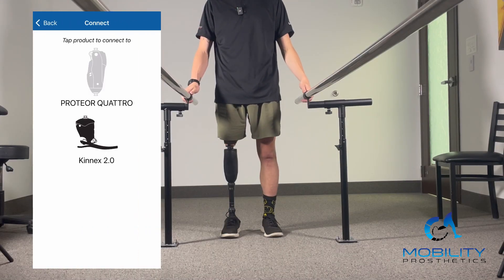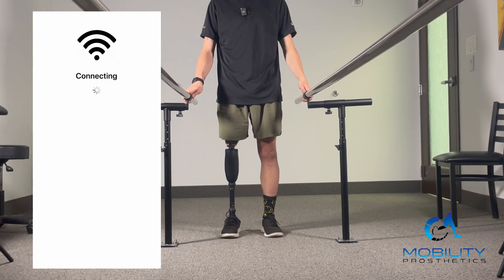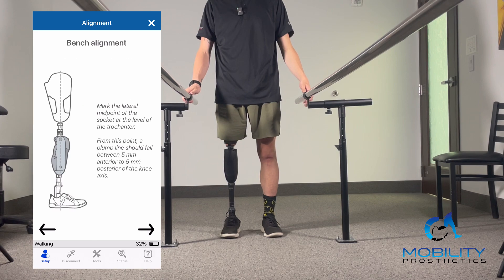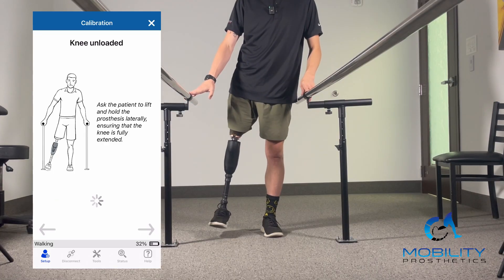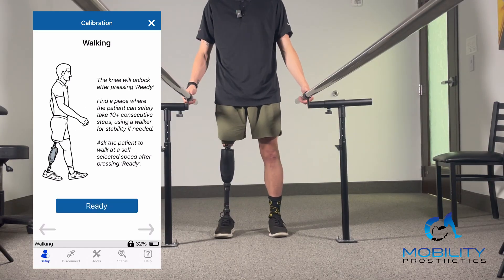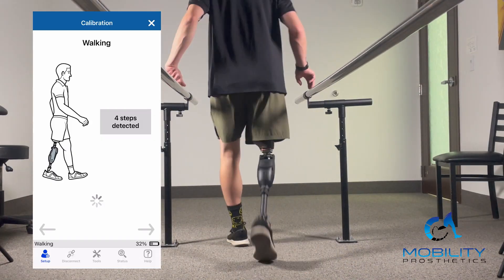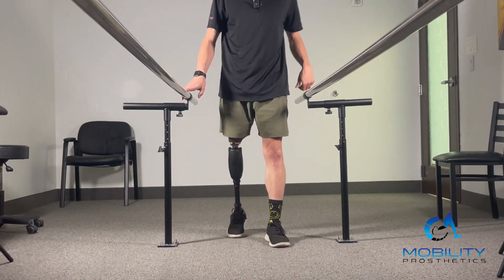On setup, we go into the Gait Lab app and click Quattro. I'm already paired so we skip the PIN entry. You go to the full setup at the top and click through the arrows — it gives you bench alignment, flexion stops, then a quick knee unloaded, a knee loaded, and then 10 steps for calibration, followed by static alignment. After that it goes through the settings and you're really done.